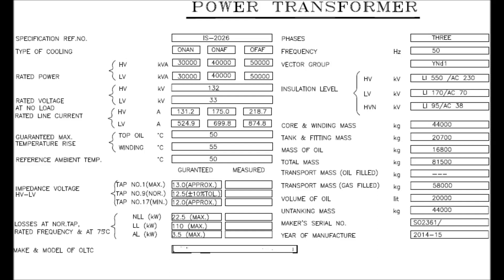Hello friends, today I will discuss about nameplate details of a power transformer. In this video I will discuss about nameplate details of a power transformer of rating 50 MVA capacity, with rated voltage of HV side winding at 132 kV and LV side voltage at 33 kV, and vector group of YNd1 type.